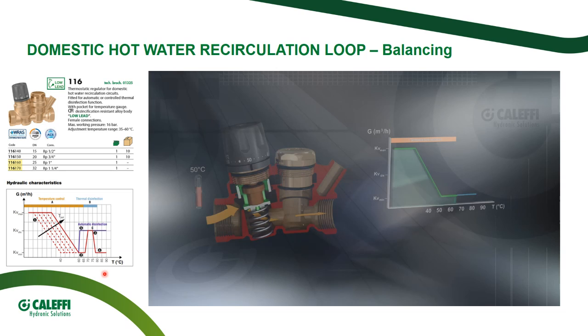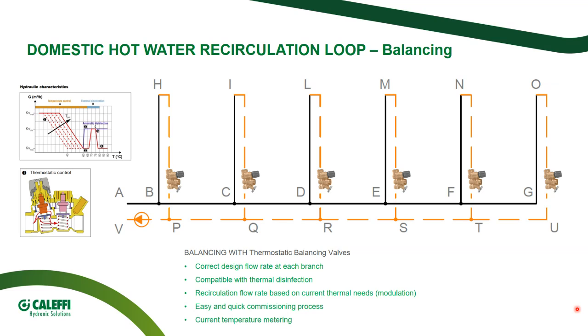So let's suppose to install these devices replacing the double regulating valves, and this is the situation. So what is my scenario? I am granting the correct design flow rate to each branch. This system, we will see in 2 minutes, can be compatible with thermal disinfection. The recirculation flow is based on the current real thermal needs of the ring of the loop. In other words, the valve is able to modulate, granting me energy saving. The commissioning process is very, very easy. It is enough to rotate the knob up to the desired value. And the valves are also equipped with a pocket where you can install a temperature gauge or temperature probe in order to meter the current temperature throughout all the building and in every single branch.